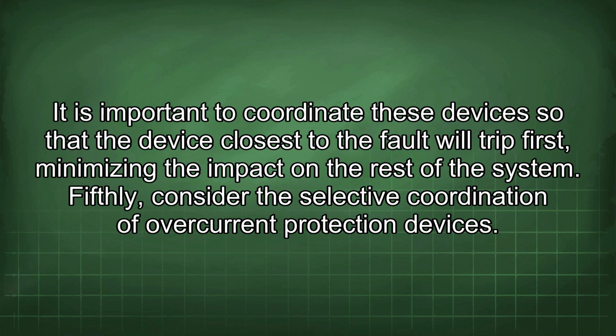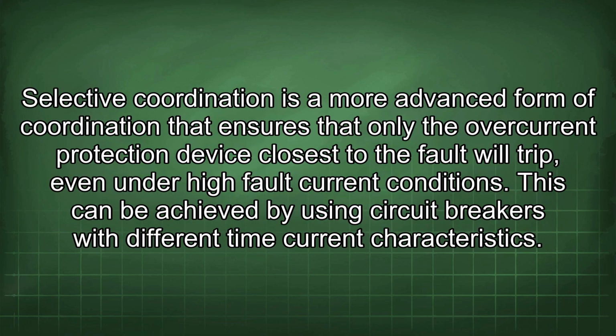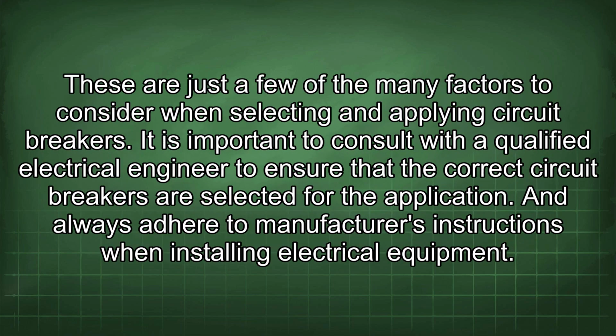Fifthly, consider the selective coordination of overcurrent protection devices. Selective coordination is a more advanced form of coordination that ensures that only the overcurrent protection device closest to the fault will trip, even under high fault current conditions. This can be achieved by using circuit breakers with different time current characteristics. These are just a few of the many factors to consider when selecting and applying circuit breakers. It is important to consult with a qualified electrical engineer to ensure that the correct circuit breakers are selected for the application, and always adhere to manufacturer's instructions when installing electrical equipment.